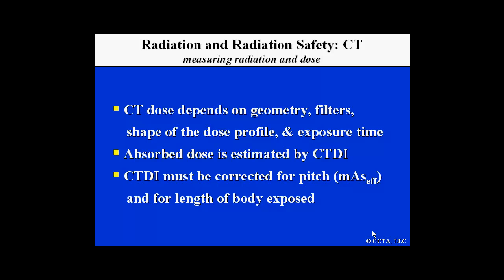CT dose depends on the geometry of the scanner, the filters applied — especially the use of a bow tie filter — the shape of the dose profile, and the exposure time. The absorbed dose is estimated by the CTDI apparatus. However, the CTDI must be corrected for pitch of an actual study and for the length of the body examined.